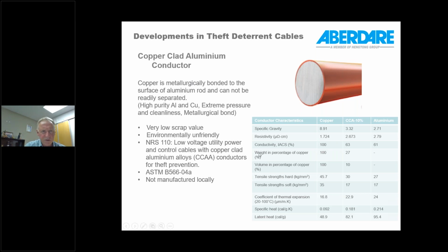If we move on to the alternative conductor material of copper-clad aluminium, I must say that this has also not been successful, and I would say mainly to the extent that manufacturers were not comfortable with the problems associated with this particular conductor and the cables. It's manufactured in a similar way, or in the same way as copper-clad steel is manufactured, and you also need high purity aluminium and high purity copper, because you need this metallurgical bond, which is created in the same way as you do for the copper-clad steel. These metals cannot be separated. They can only be separated if you make a poor quality product, so they're not intended to be a loose cladding onto the aluminium. It's supposed to have a solid bond.